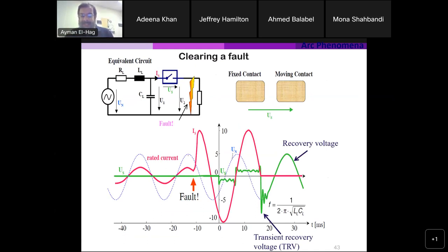The moment it's cleared, we have what we call transient recovery voltage. When the fault is completely cleared, you have no current at all and the voltage is restored, but it doesn't restore smoothly. There will be some transient here, and this transient will have a frequency equal to 1/(2π√LC), where L and C are the inductance and capacitance of your system. So this transient, or TRV, is a phenomenon that happens across the circuit breaker when we open the fault.